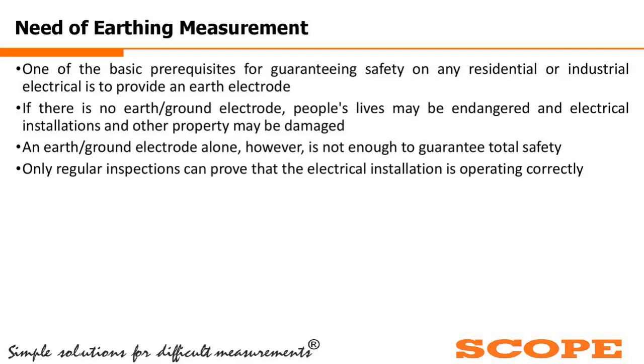But in any system, a single electrode alone may not be sufficient to give a 100% guarantee of total safety. So we are talking about parallel earthing points or parallel earth electrodes. From that only the advanced consideration has come, when we started talking about the earth mesh or the copper mesh at the bottom, so that our target is to increase the quality of earthing, and whether all these things are working properly or not needs to be revalidated over a period of time. Only regular inspections can prove that the electrical installation is operating correctly.